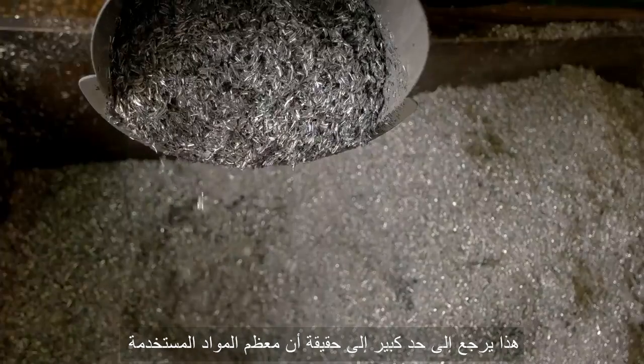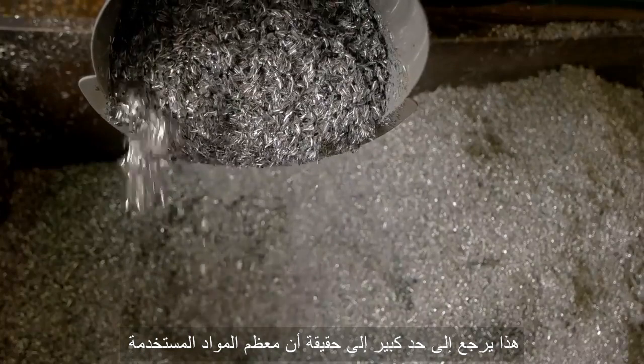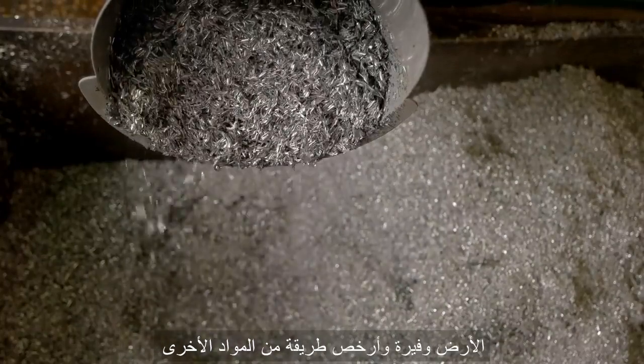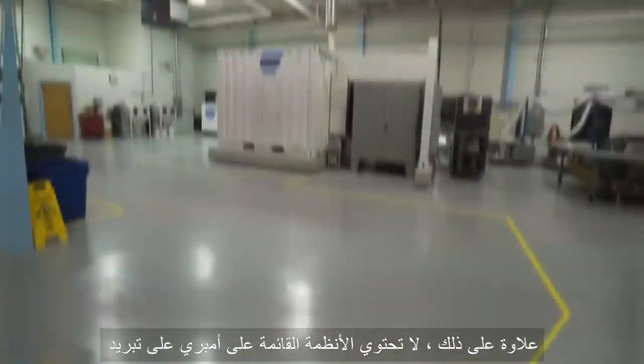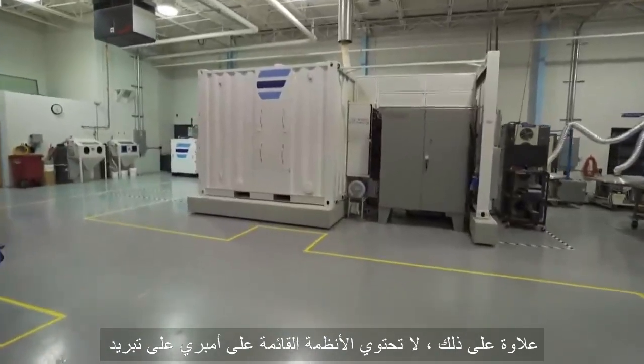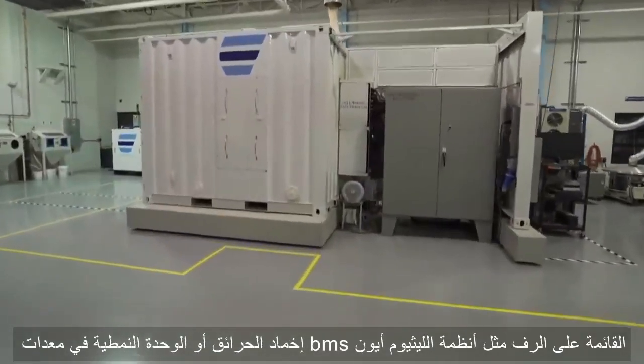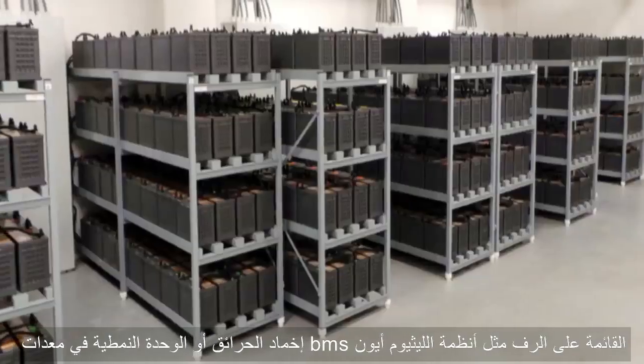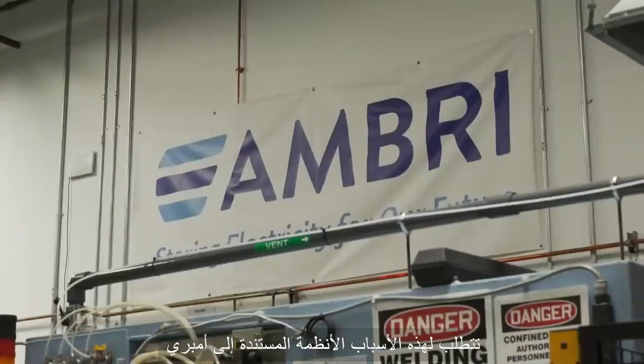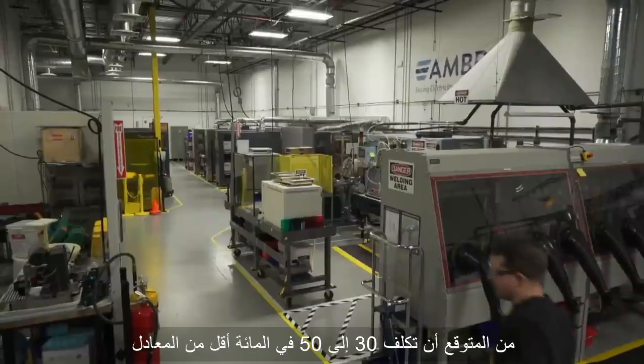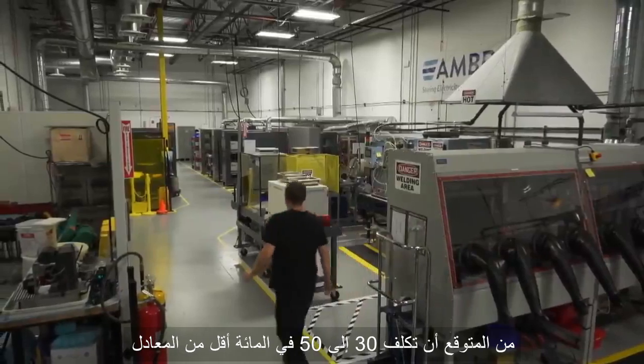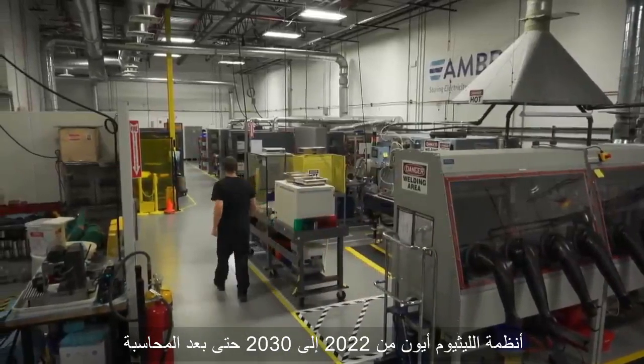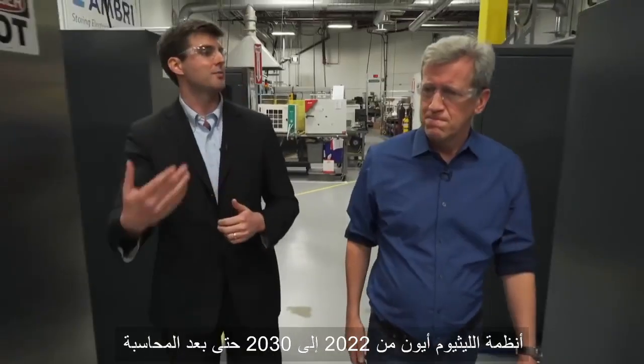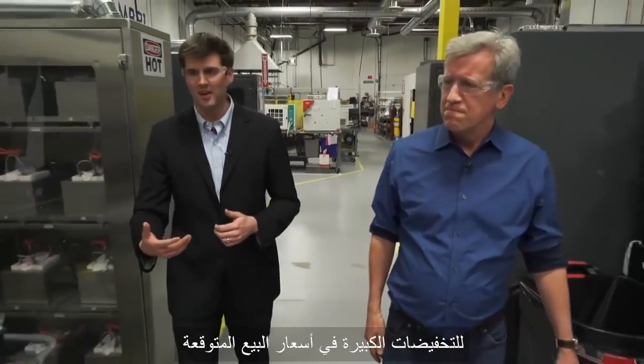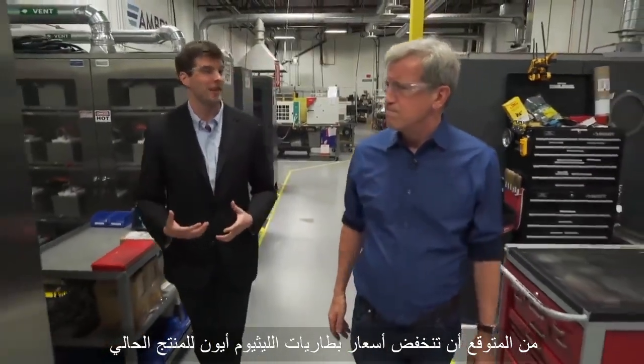This is largely due to the fact that most of the materials being used are earth-abundant and way cheaper than other materials. Furthermore, Ambri-based systems do not have cooling, fire suppression, or module and rack-based BMS equipment, as lithium-ion systems require. For these reasons, Ambri-based systems are projected to cost 30 to 50% below equivalent lithium-ion systems from 2022 to 2030, even after accounting for the aggressive cell price reductions that are forecast for the incumbent product.